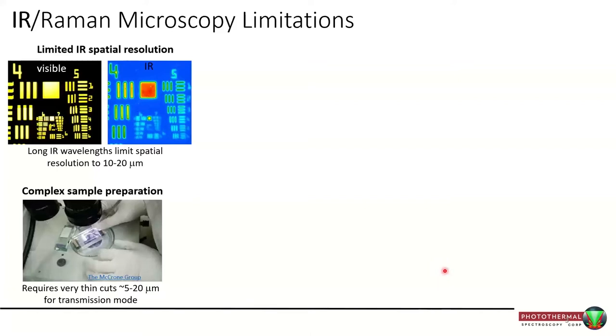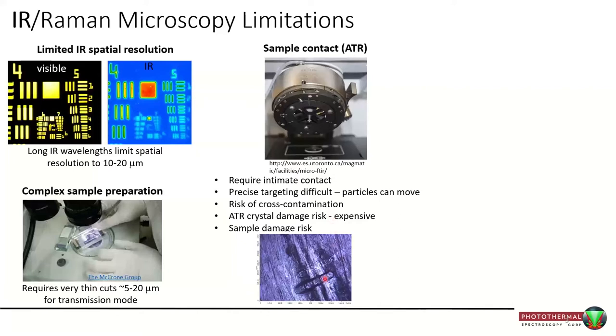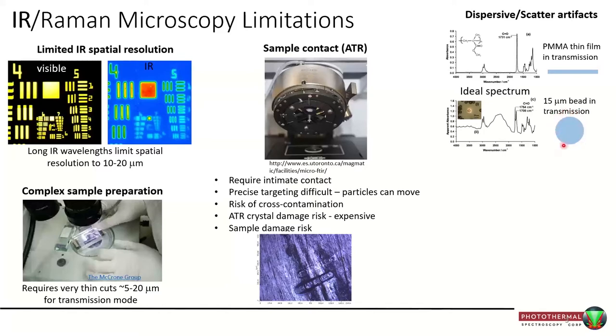Sample preparation is also complex — the best spectra are obtained with thin cuts, typically 5 to 20 microns, which can be very difficult. Some of those issues are mitigated with ATR, but that requires direct intimate contact and can be difficult to target, with risk of cross-contamination. One under-appreciated issue is dispersive scatter artifacts. The same PMMA material collected as a thin film versus on a bead looks very different, making infrared spectra sample shape, size, and surface roughness dependent.